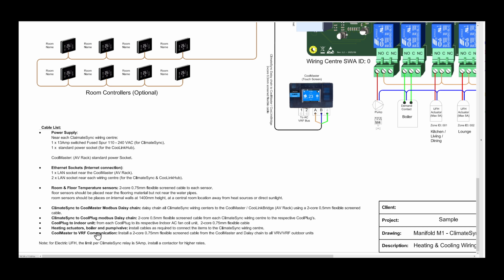Heating actuators, boiler and pump, as we explained on the connections over here. CoolMaster to VRF communication, 2-core 0.75 millimeter flexible screened cable. That's the daisy chain to all the VRF outdoor units. That is very important, and this will allow also diagnostics.